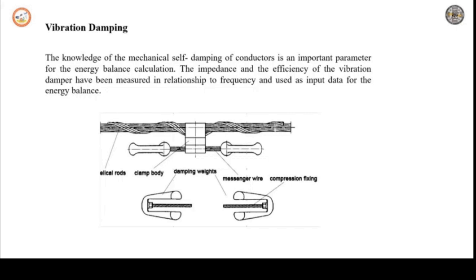What are the factors, by the way, affecting the conductor vibrations? That is very important to know. The various factors: one is atmospheric conditions like icing, rain, and high wind velocities. Span of the conductor will also affect, tension in the conductor will affect, and you cannot ignore conductor configuration. That design is very important. Types of clamps that we use are also important, which affects the conductor vibrations, and height of the towers also affects conductor vibrations.